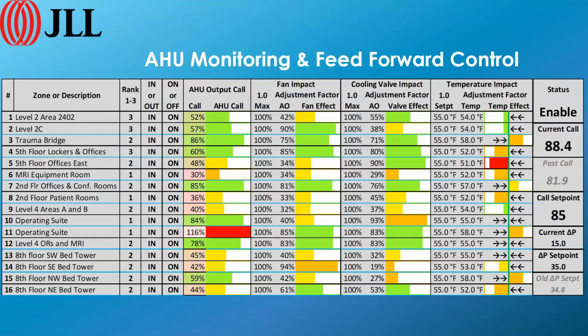In this case here, it's from a hospital. Because of the nature of that hospital, we took all of the zones, but you don't necessarily need all of them. In a typical building, you'd probably use 16 or maybe 18 zones. East, west, north, south, the corners of the building, and then you'd pick 4 or 5 or maybe 6 zones inside the building that are crucial, or meeting rooms or something like that. And you pick those zones, and those are the ones that you'd monitor.